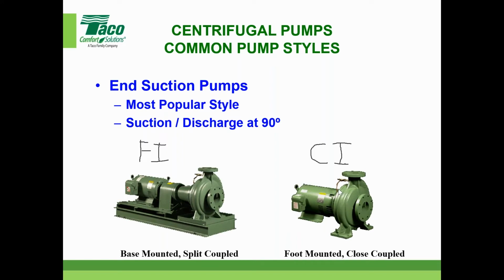Most people on the close coupled pumps, maybe for a base mount, you may not see too many, but once you get over 7.5, 10 horse, I would recommend this type over here. You don't have to move the piping to change the seal on this split coupled pump. The motor doesn't have to be lifted out of the way, it may just need to be loosened and twisted to give enough room to get that spacer out. Nonetheless, your maintenance is a lot easier.